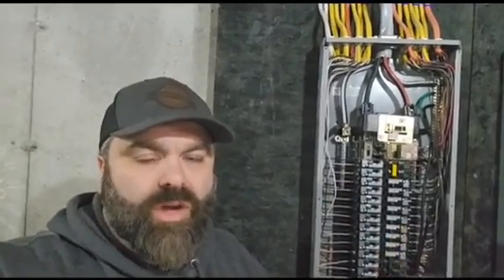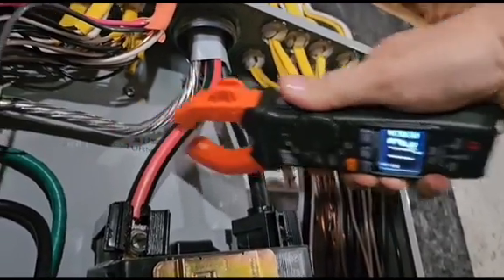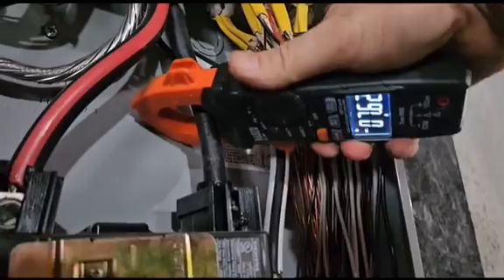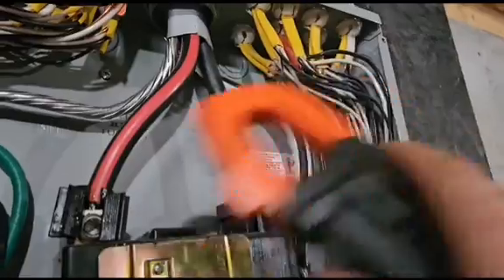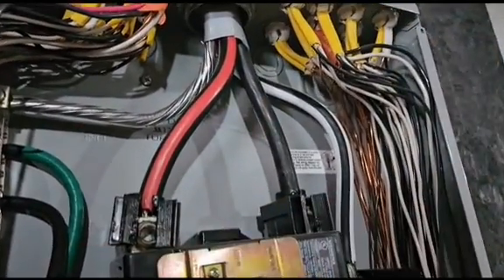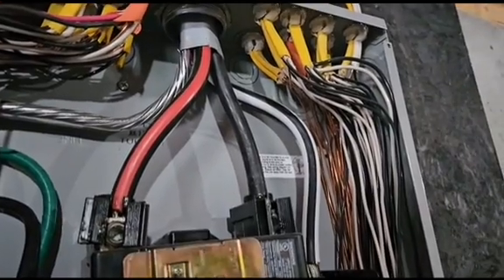This is what we're talking about here. We got about 11 amps on that hot and about 7 amps on that hot. If you do the math between the two, you end up with 4 amps on the neutral. All the amperage coming off the transformer has a path back to the transformer. None of it is canceled out. If it leaves the transformer, it goes back to the transformer.